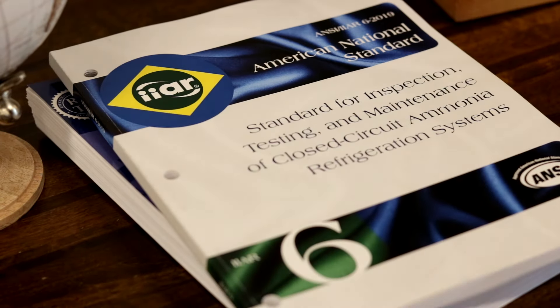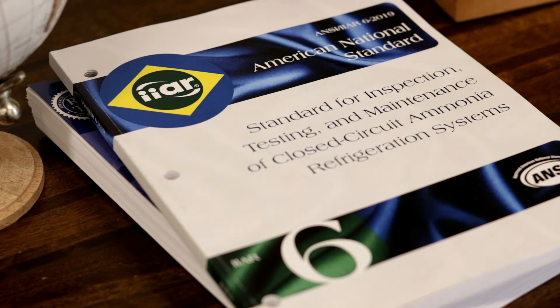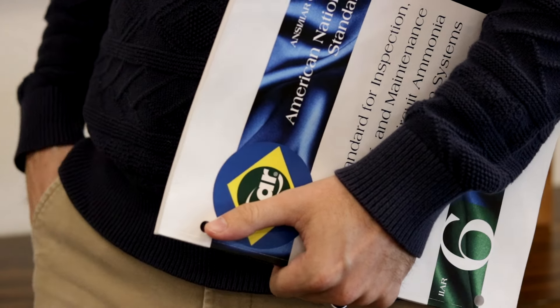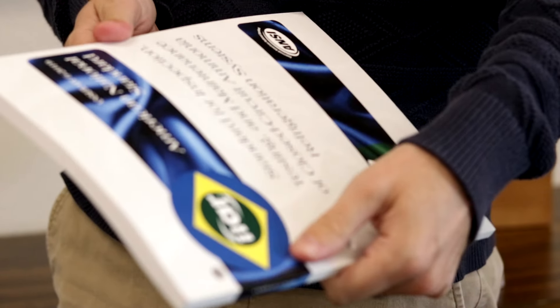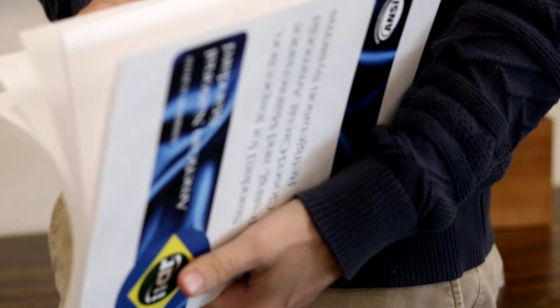The checklist questions contained in IIAR 6 Appendix B are derived from a legacy document named IIAR Bulletin 109. For years, the Bulletin 109 checklists, or B109s, served as the gold standard for documenting annual mechanical integrity inspections for ammonia refrigeration equipment. In 2019, IIAR retired Bulletin 109 when the first edition of Standard 6 was published.